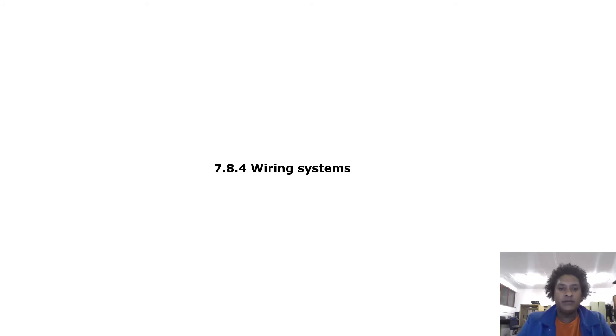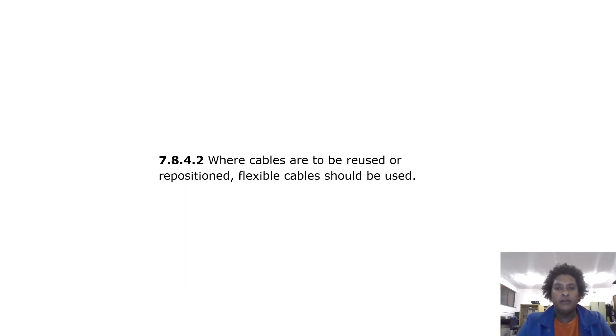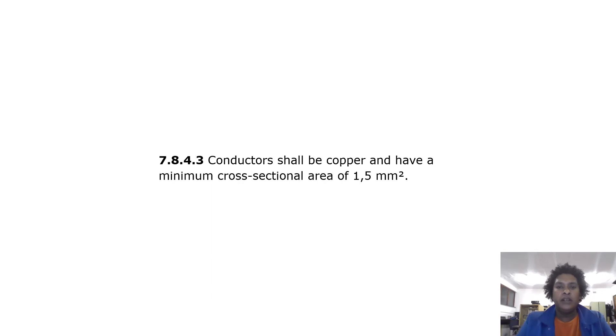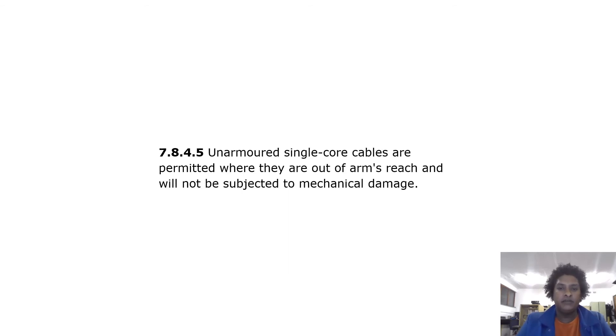Wiring systems: cables shall be selected or protected to withstand likely mechanical damage. Where cables are to be reused or repositioned, flexible cables should be used. Conductors shall be copper and have a minimum cross-sectional area of 1.5 mm². Uninsulated live conductors are not permitted. Unarmoured single-core cables are permitted where they are out of arm's reach and will not be subjected to mechanical damage.